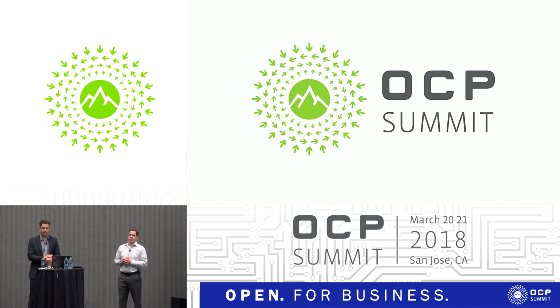So going back to your initial statement on this trend towards shipping racks full of equipment, pre-tested, pre-deployed, right? We do a lot of that. One of the problems we have, and we've done large surveys of racks that are available in the market, is that you can't ship them full of equipment because they can't pass shipping shock and vibe, and these types of things.